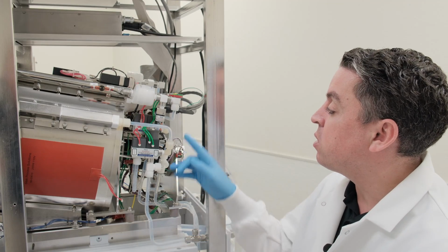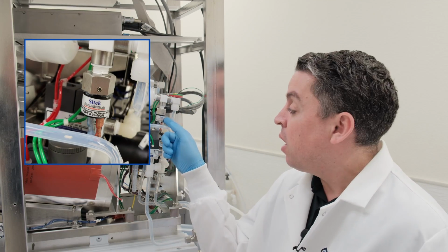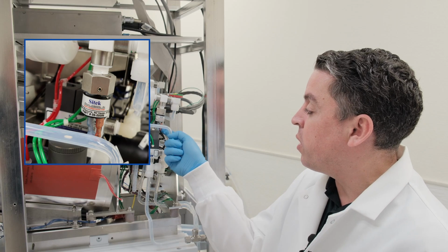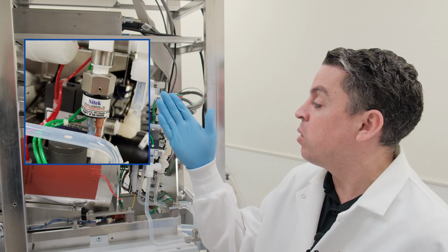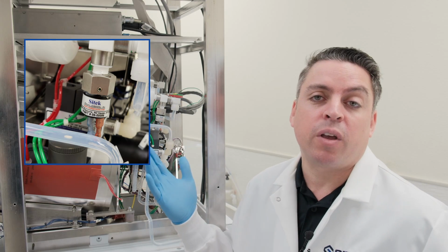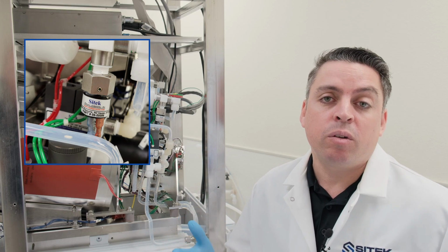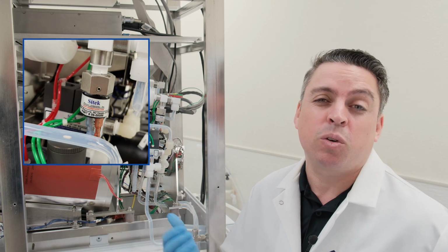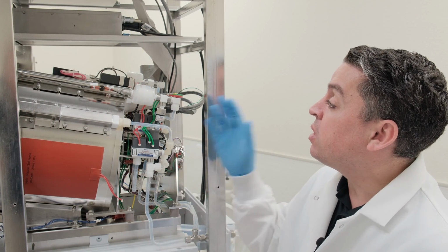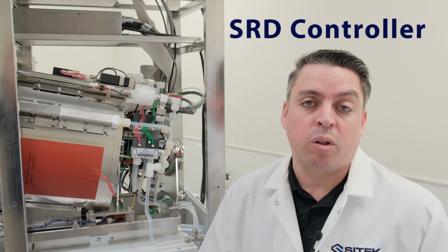The 2 common ones are going to be, first, this 8 psi pressure switch failing. And so if we want to test this out, what we can do is remove the leads from the bottom, jumper them together, and then if our problem goes away, you know that the pressure switch has failed. This is a common part that you should have in inventory already, and if you don't, we can get that on order and actually overnight it to you same day if that's what you need to get your tool back up and running.